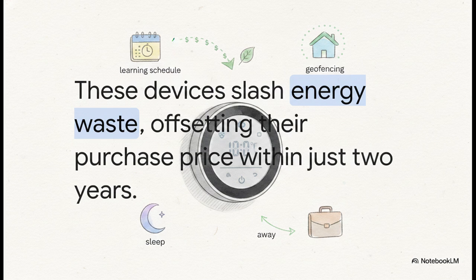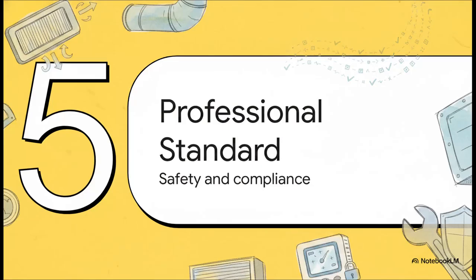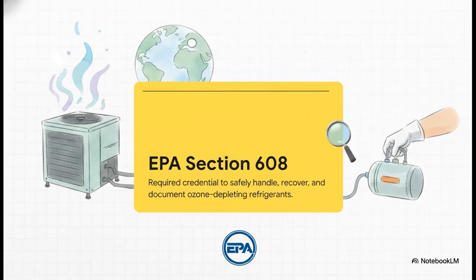That brings us to our final section, Part 5, the professional standard. When dealing with hazardous materials, the stakes are incredibly high. Older systems often contain outdated refrigerants, like the R22 we mentioned earlier, which actively deplete the ozone layer. Handling these chemicals requires strict EPA Section 608 certification, ensuring technicians are legally and safely recovering the refrigerant, protecting both your system's integrity and the global environment.